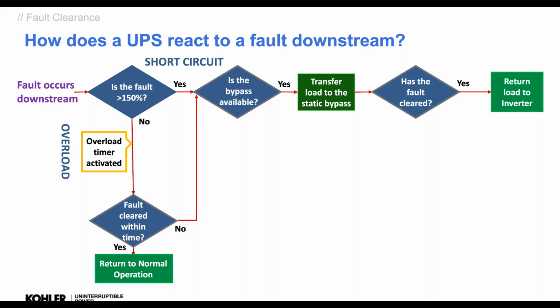And if it clears the fault, great. Typically, the UPS will transfer itself back online. It will leave an alarm up to say it's had a short circuit. But if it doesn't clear it, something's got to give. Okay, either fuses internally on the bypass or an upstream protection to the UPS. It's not ideal, obviously. We shouldn't design it like that, but that's what will happen. Okay, something has to give if we've got a short circuit.